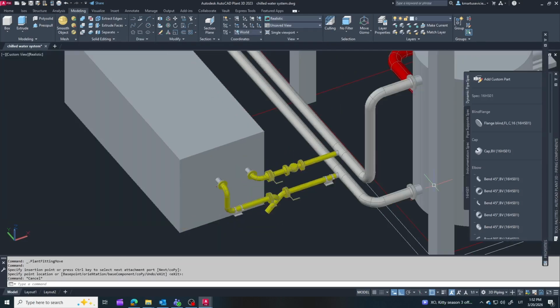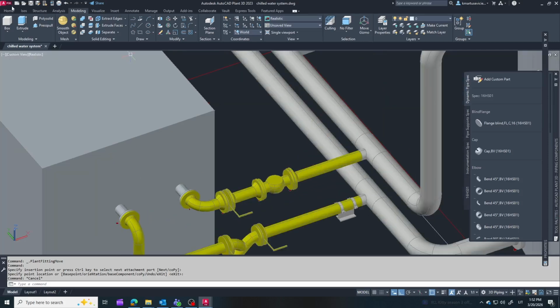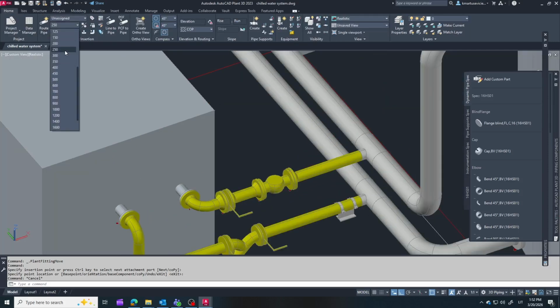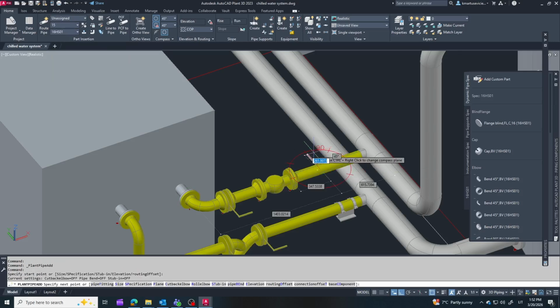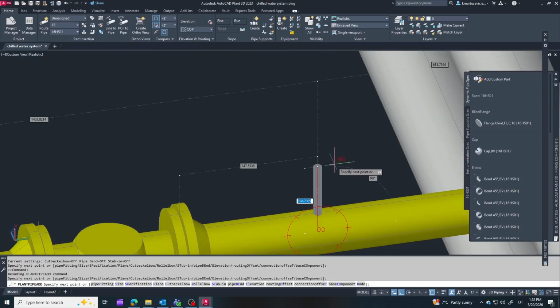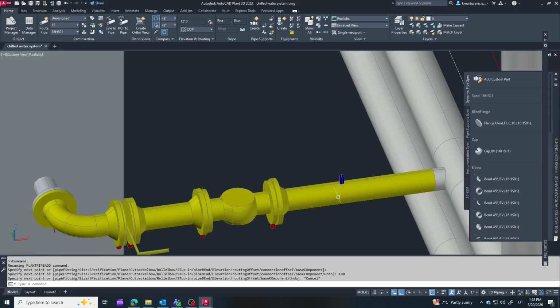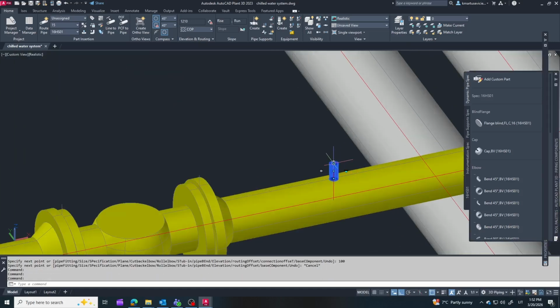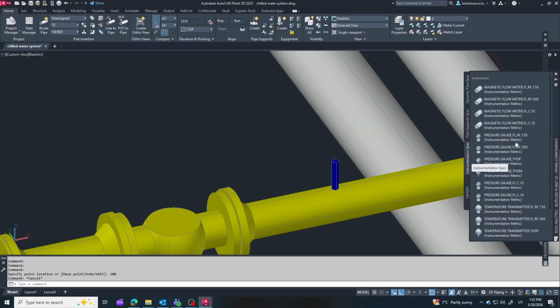Let's also talk about the thermometer on the outlet line. Its purpose is simple: to quickly check the temperature of the water leaving the chiller. This helps us verify that the chiller is operating correctly. In addition, I install a thermometer on the inlet manifold to the chillers and on all outlet lines. This allows us to monitor both supply and return temperatures across the system.